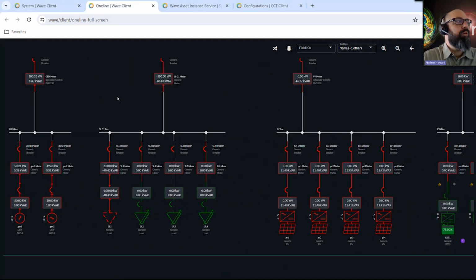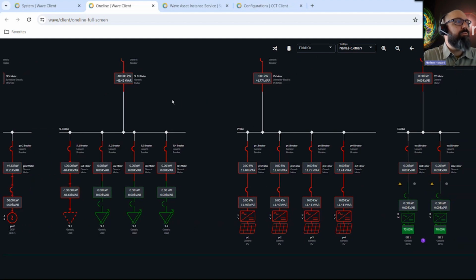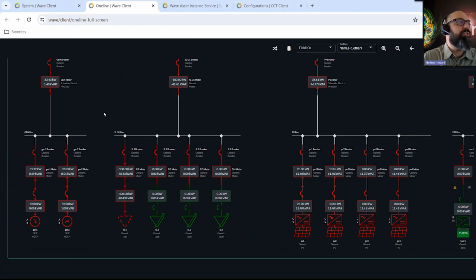So right now we're running purely on conventional generation, but as renewable energy becomes available, we'll ramp up those PV profiles, start producing some energy from our PV inverters. Those will start feeding the load. And as a preferred resource, the lowest carbon resource available to us, we'll start backing off the conventional generation as that renewable energy ramps up. And if sufficient renewable energy is available, we'll even shut down one of the excess gens.